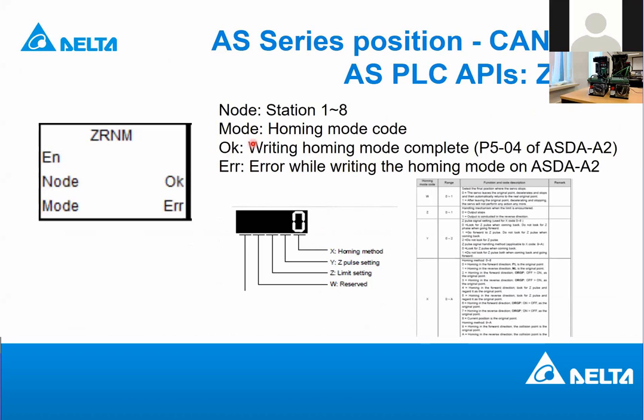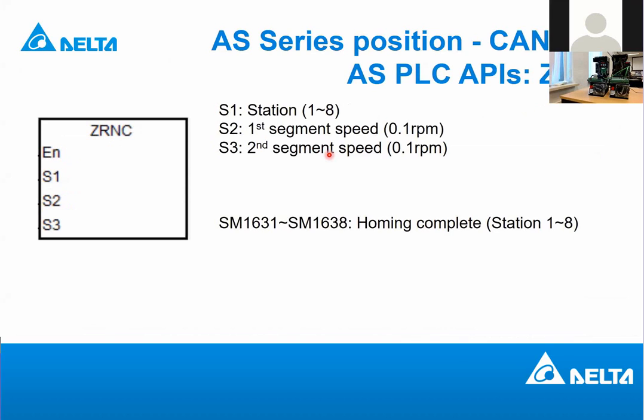So now we are going to do the homing. We have already chosen homing mode as mode 4. This is a video like I told you. This is the homing command. When this is triggered, it will move our drive to home. Once the homing is complete, this flag will be triggered to show that the homing is complete.